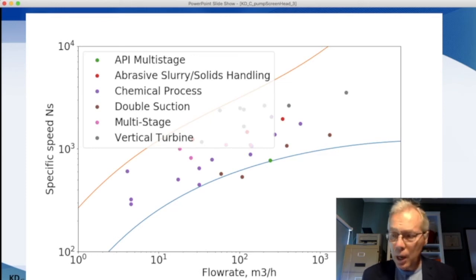All that we need to do now is select different combinations of pump speed and the number of stages and see where they fall on this map of specific speed and flow rate. I use Python for these calculations. You could use a spreadsheet.